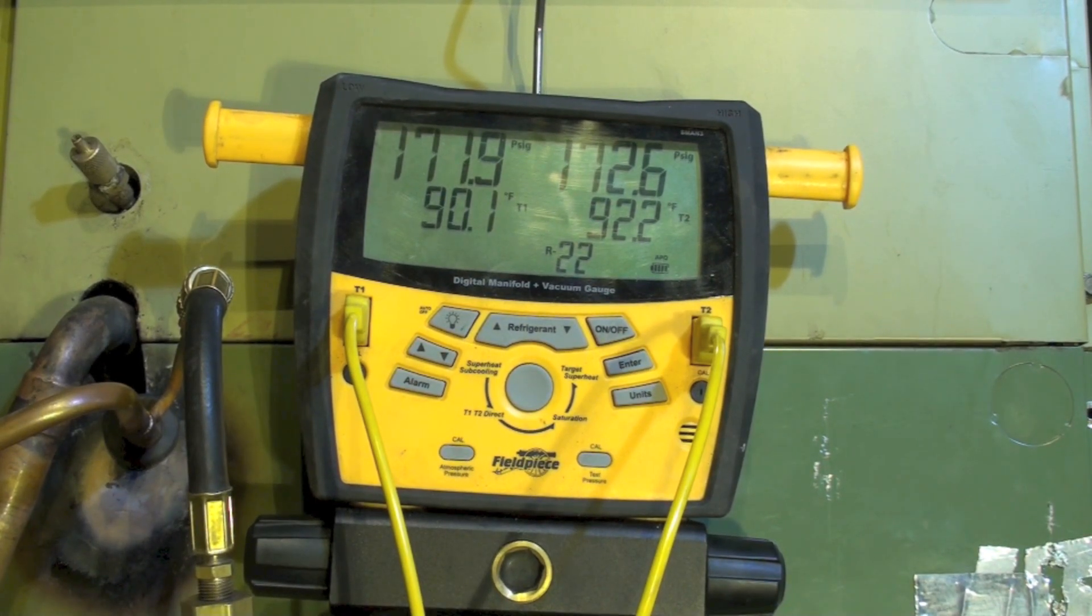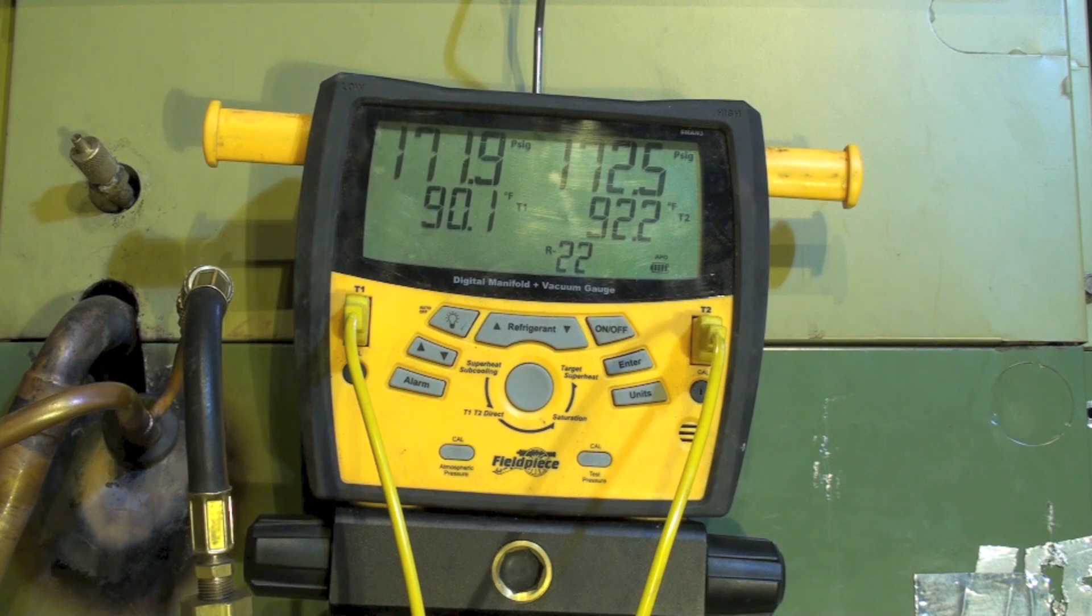Okay, I've been asked to do a pump down on this thing. It doesn't have the valves for a pump down, but I can shut off the suction line valve because I do have a suction line valve and I have a common suction, so I can see how much of a vacuum the compressor will pull. I'm going to go ahead and do that now.